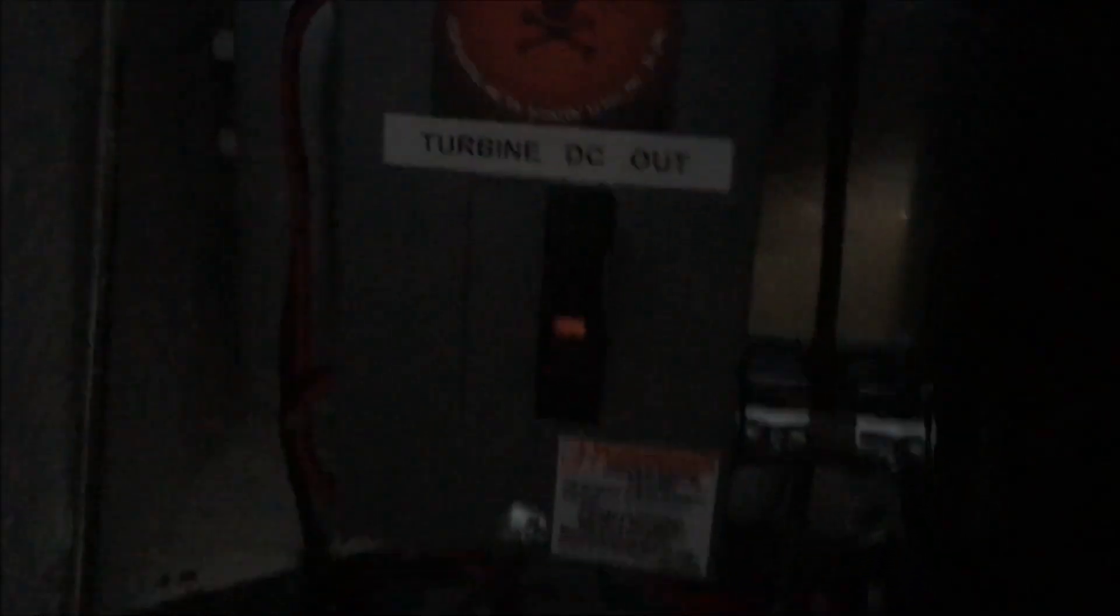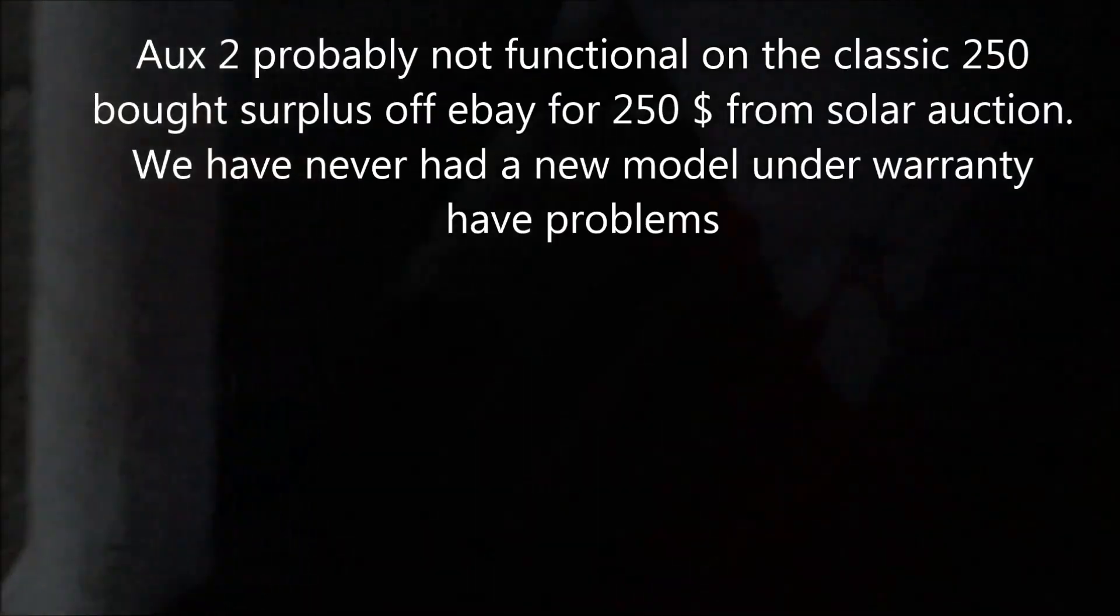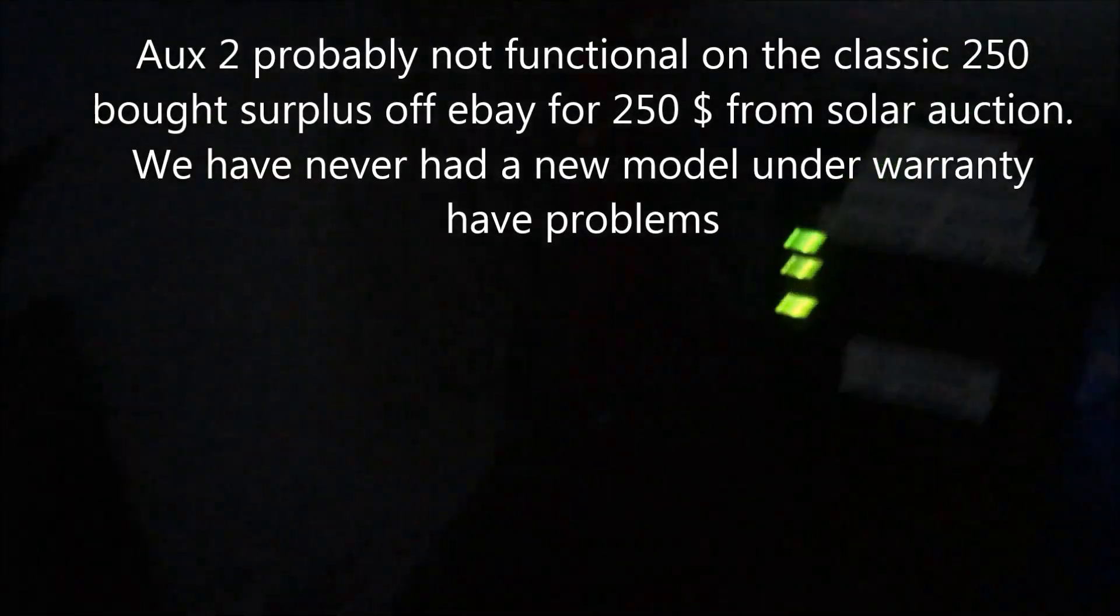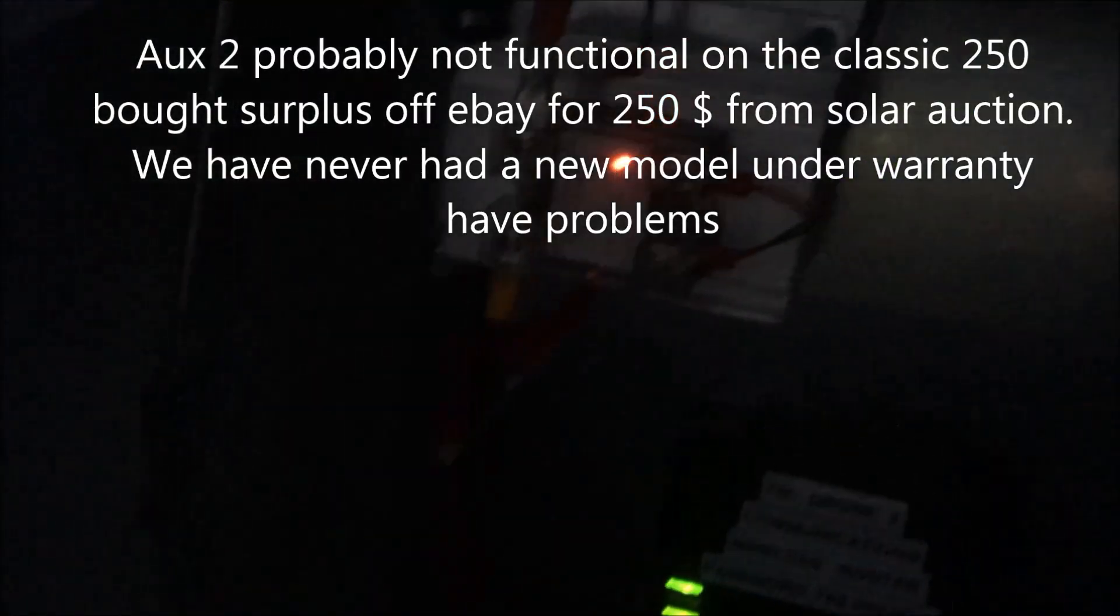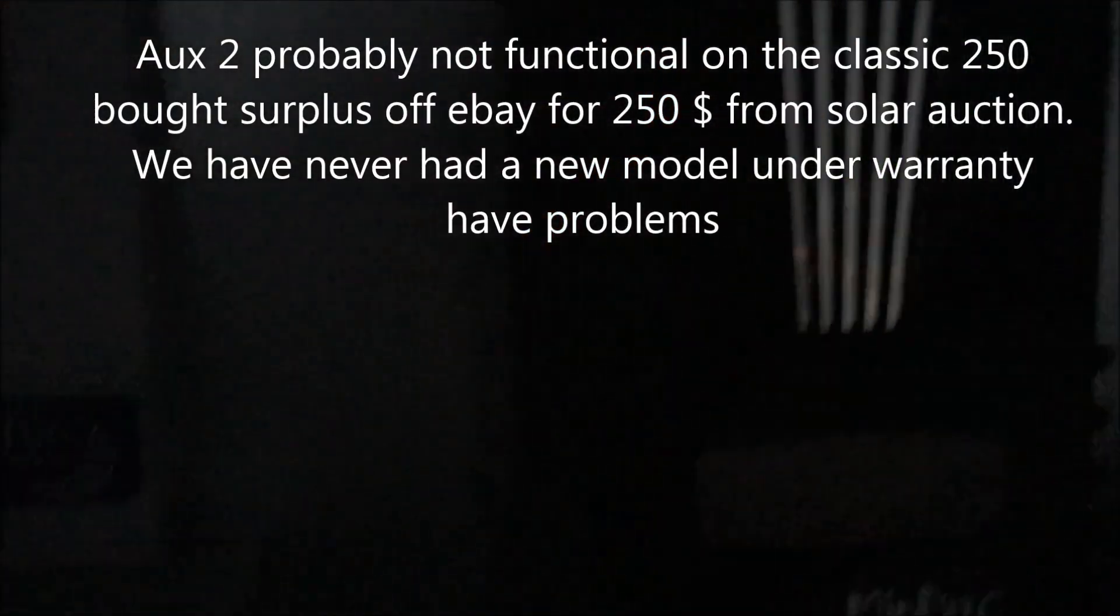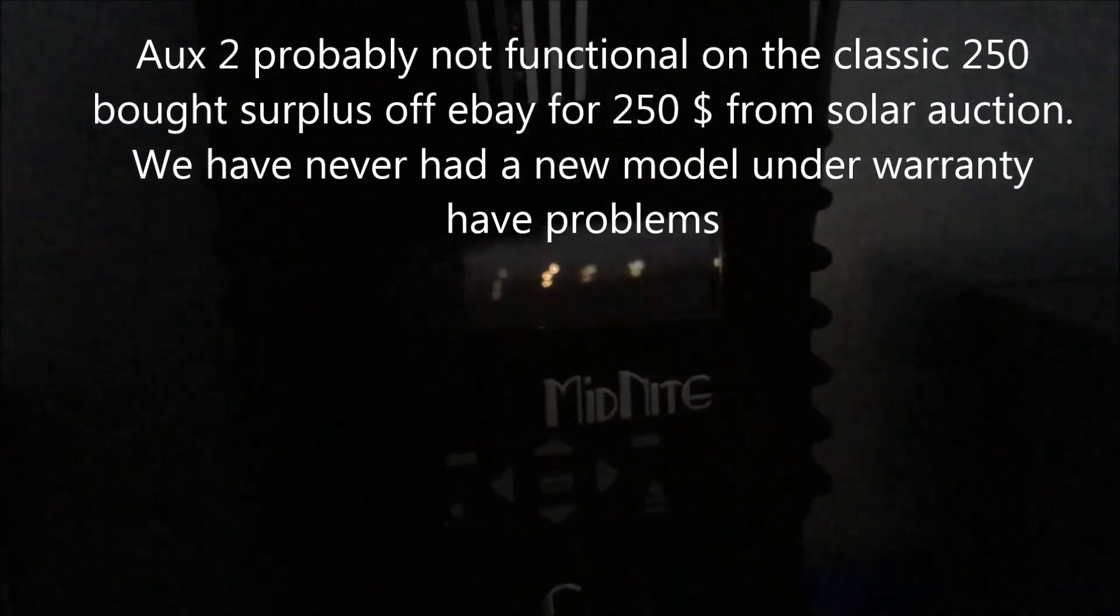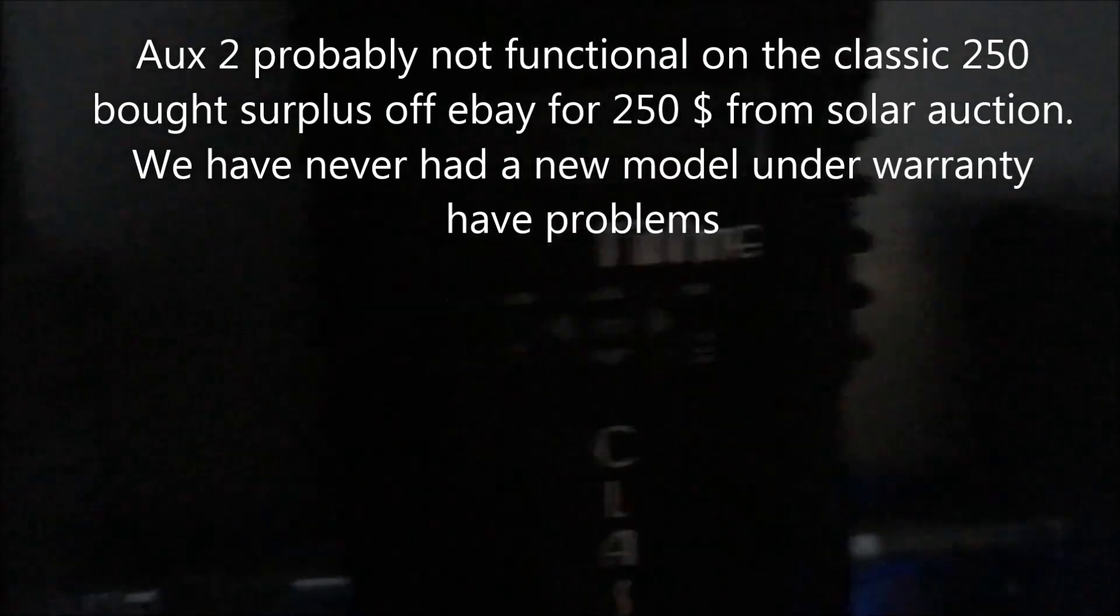Let's just run over there and take a look inside the cabinet. It's a little bit dark. Yep, we lost the breaker on the DC out. You can see that we are diverting to our diversion load that's coming off of the PV. The PV is set for the diversion because there's a problem with aux 2.